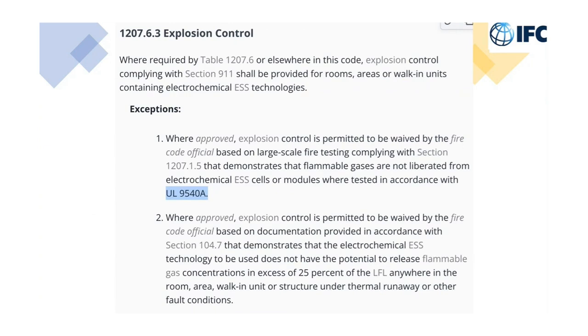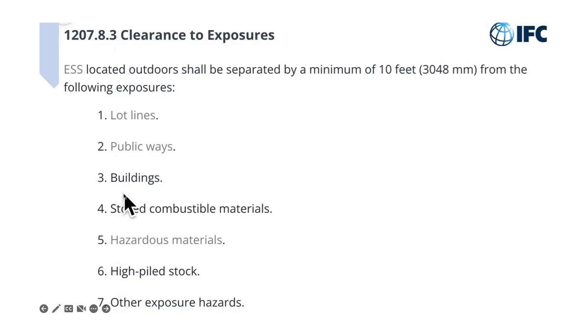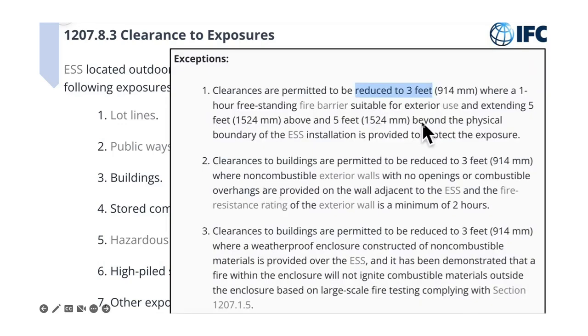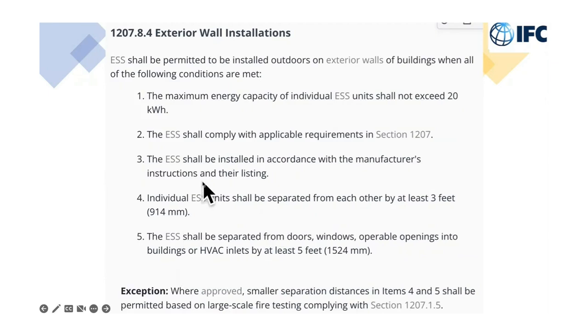Another thing too is since that fire that they had at APS, that's Arizona, they started making a lot of these so they're not walk-in containers, but you access everything from the outside. It's still a container, but you have doors from the outside where you get to things. That also gives you more room on the inside if you don't have to have a walking space and separation of things inside. So clearance, lot lines, and all that kind of stuff: 10 feet from buildings with exceptions, reduced to 3 feet in certain places. Exterior walls, installations, we kind of talked about.